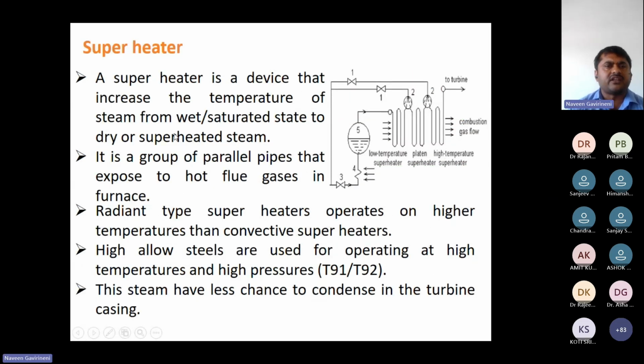There is another accessory, the superheater. We have three types of superheater arrangements: primary, secondary, and final superheater. The final superheater is the OEM final superheater, where flue gas goes through the second pass, while primary and secondary are in the first pass only. So we are using the radiant type of superheater, and while operating the superheater we should be more cautious. Why? Because the temperature at the superheater is higher than in the other devices. We are getting 540 degrees at the end of the superheater, and the OEM also supplies 540 to the turbine.